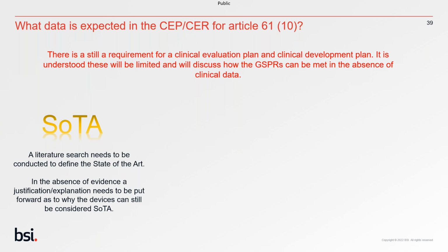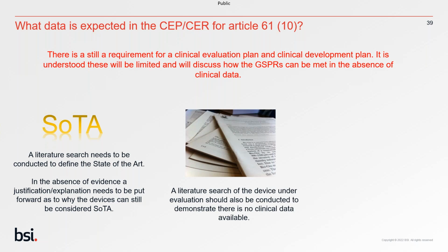We know, of course, that sometimes these devices are not typically reported in literature. So if there is no evidence, then make sure that you always consider a justification or explanation as to why you can still be considered state of the art.